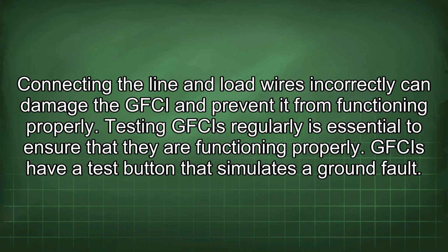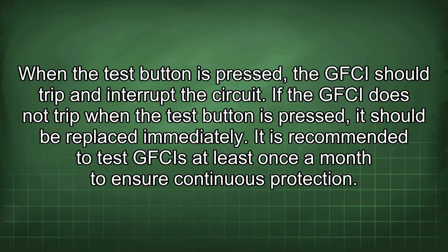Testing GFCIs regularly is essential to ensure that they are functioning properly. GFCIs have a test button that simulates a ground fault. When the test button is pressed, the GFCI should trip and interrupt the circuit. If the GFCI does not trip when the test button is pressed, it should be replaced immediately. It is recommended to test GFCIs at least once a month to ensure continuous protection.